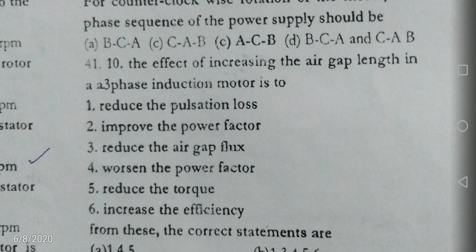If the air gap length increases, option 1, reduce the pulsation losses, is correct. Option 2, improve the power factor: if the air gap length is increasing, the power factor will decrease, because the magnetizing current value will increase and the power factor value decreases.